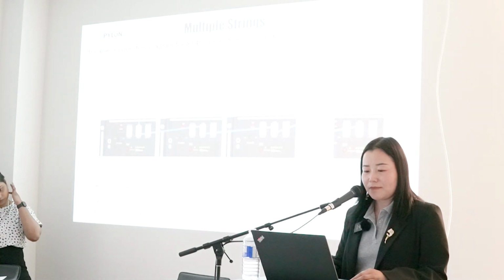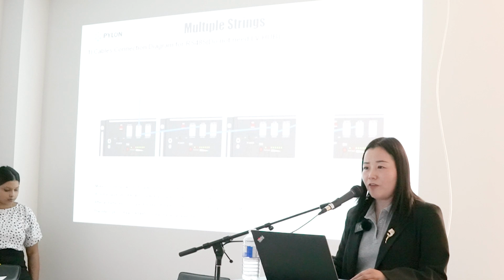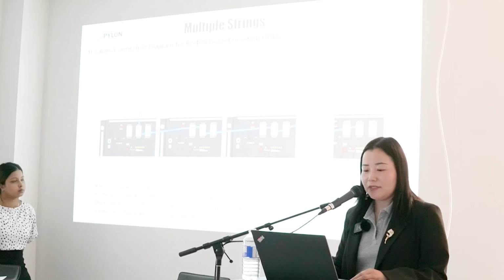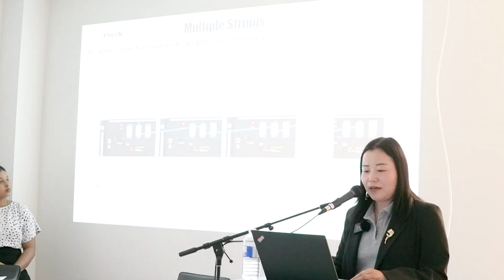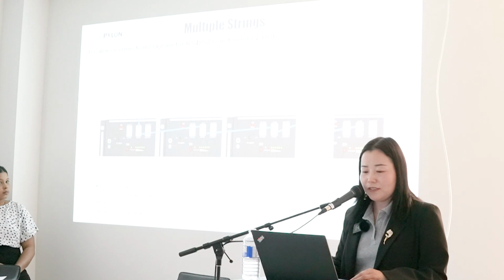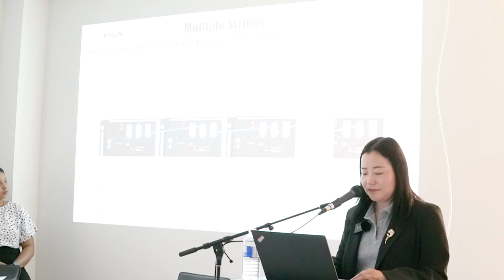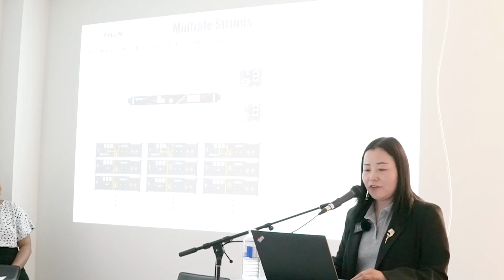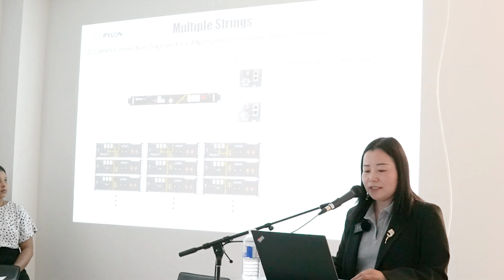For multi-strings, if we use RS-485, we don't need to use an LV hub. If we use CAN communication, we need an LV hub. For RS-485, from the picture you will see, just use the master battery from the first group to connect with the inverter. But for the CAN communication, we have to use an LV hub. Use the master battery from the first group to connect with the LV hub.